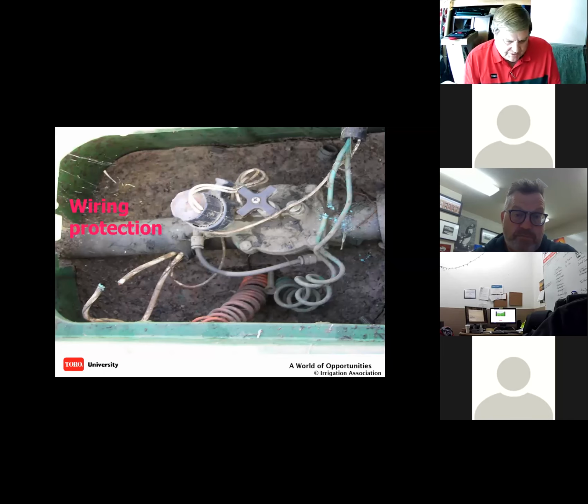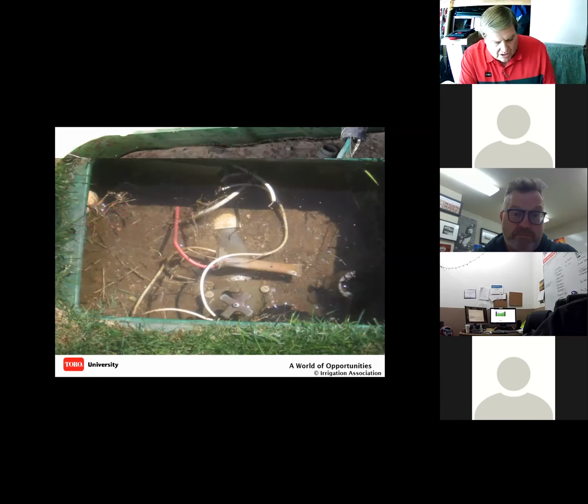Remember, a 2-wire system is running 24 volts to 30 volts to 50 volts down that 2-wire path, 24 hours a day, 365 days a year, even on holidays. With that potential, your corrosion opportunity is much greater. So be careful. Don't cut the insulation. That's compromising your system. You're going to cut it, resplice it, because connections are critical. Yeah, I love this one. There's my common wire, there's my hot wire tied together in the connector. That's a direct short. That's the common wire that should have been in there. That's not good.